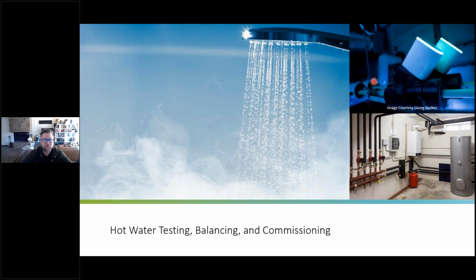And those are going to be a different type of process of testing, balancing, and commissioning than a manual balancing valve, something which you have a CV on the side and you're trying to adjust, like the circuit setter type, using the Kleenex brand type of name. That's a manual balancing valve. Those require a test and balancer, whereas the automatic balancing valves really is only commissioning. And so that's very important in order to get these systems working properly, as I demonstrated in my story early up front.